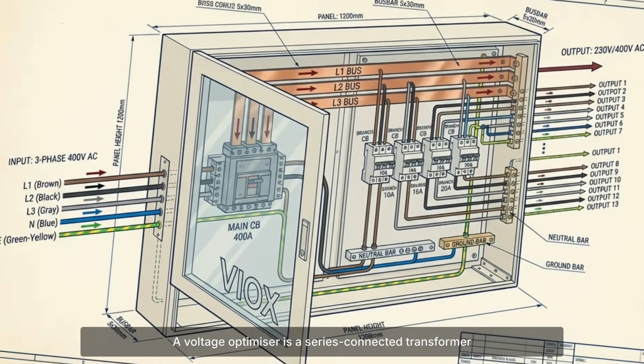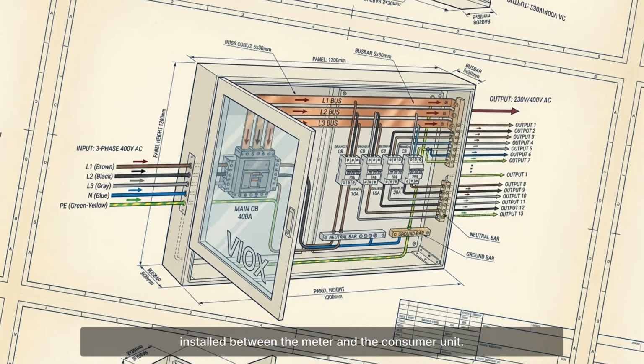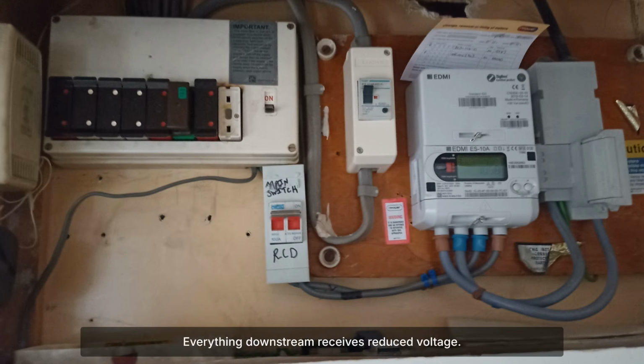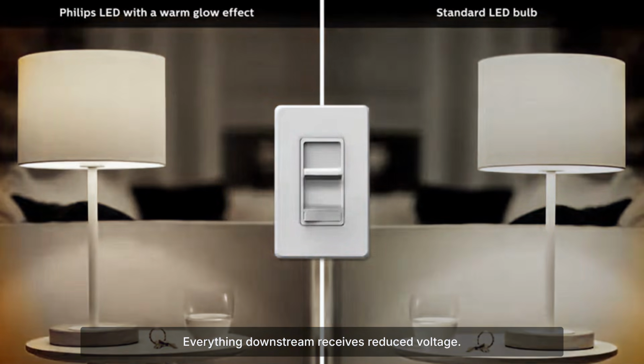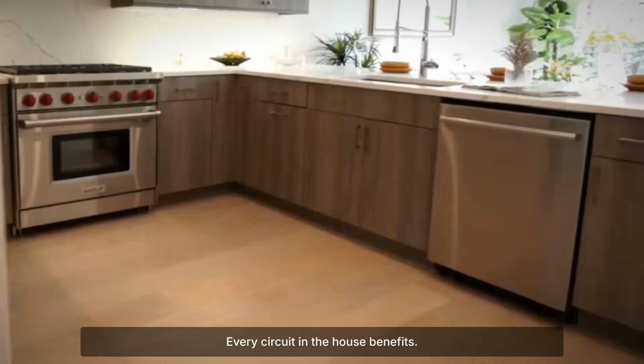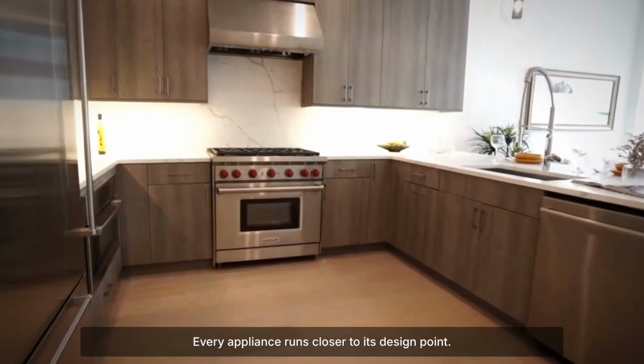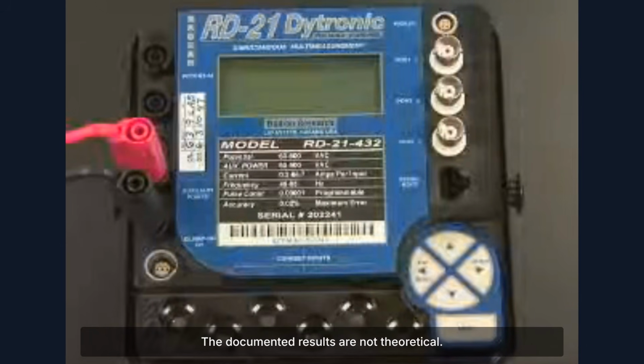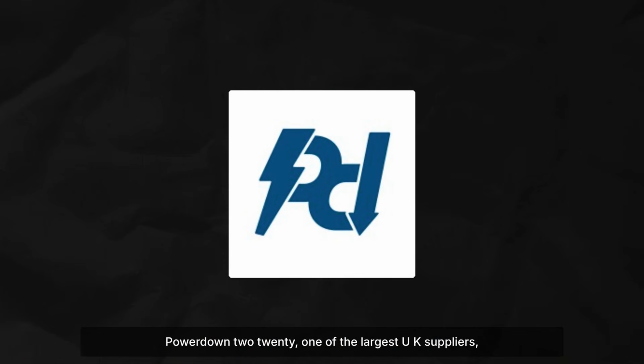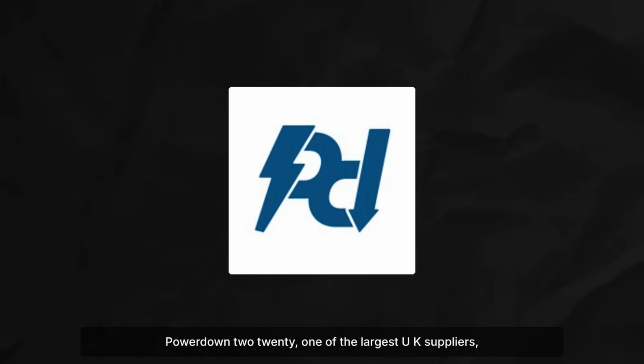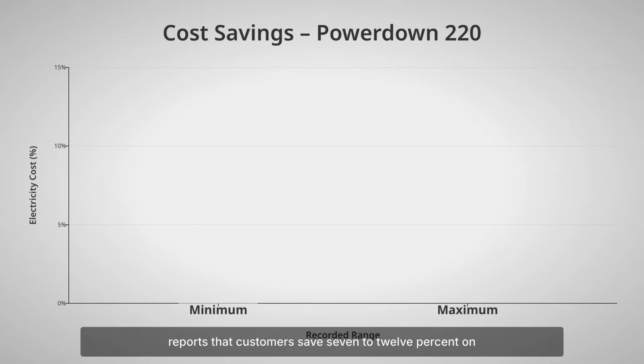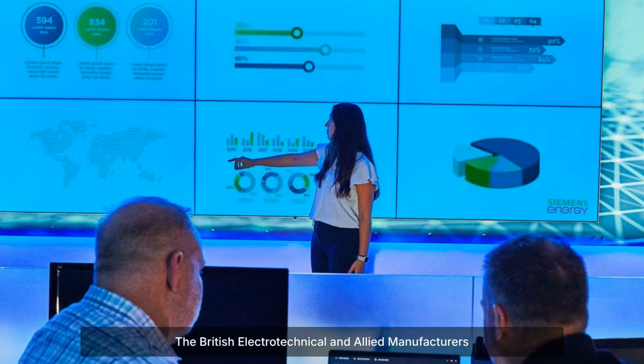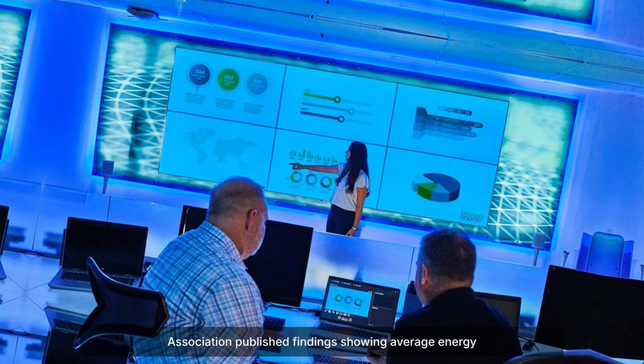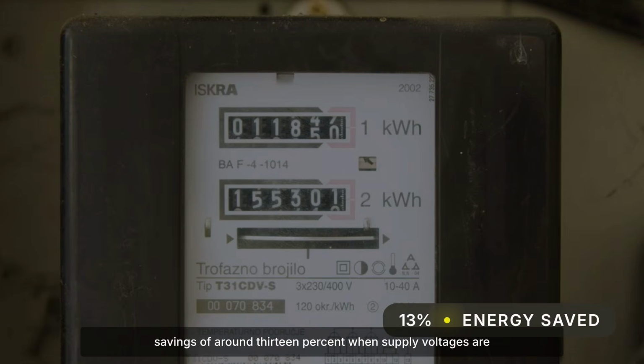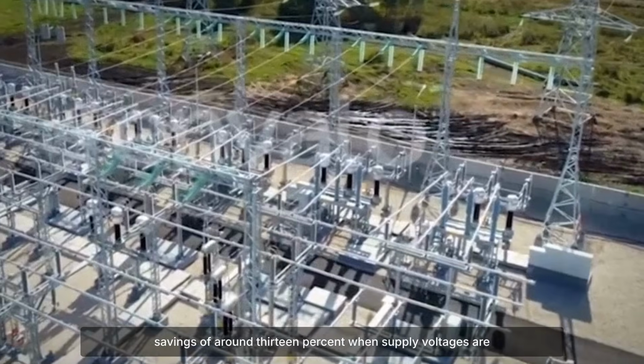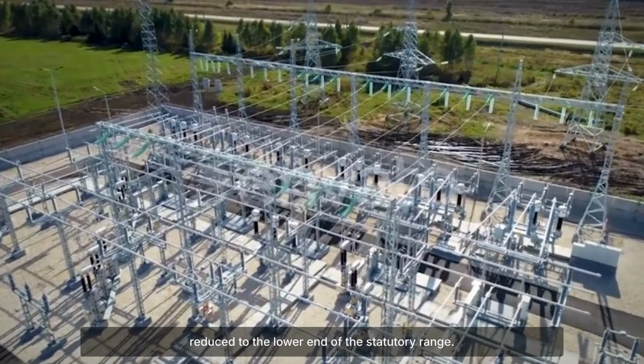A voltage optimizer is a series-connected transformer installed between the meter and the consumer unit. Everything downstream receives reduced voltage. Every circuit in the house benefits. Every appliance runs closer to its design point. The documented results are not theoretical. PowerDown 220, one of the largest UK suppliers, reports that customers save 7 to 12% on electricity costs. The British Electrotechnical and Allied Manufacturers Association published findings showing average energy savings of around 13% when supply voltages are reduced to the lower end of the statutory range.